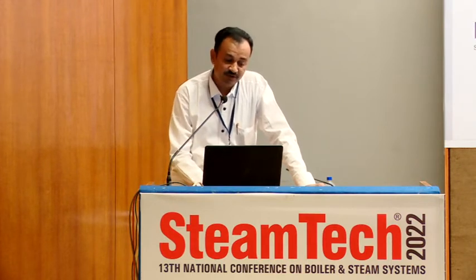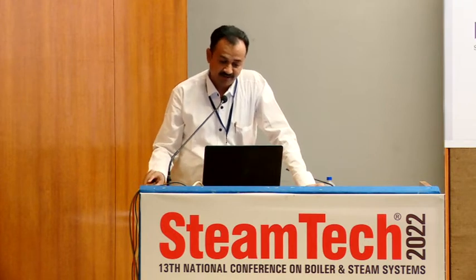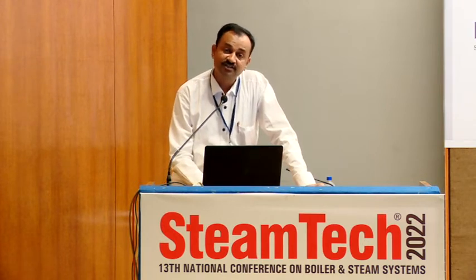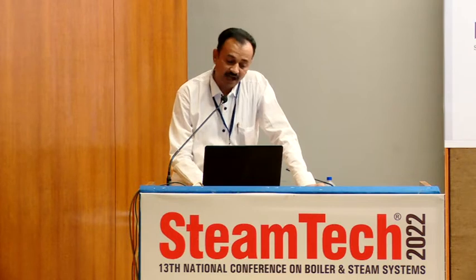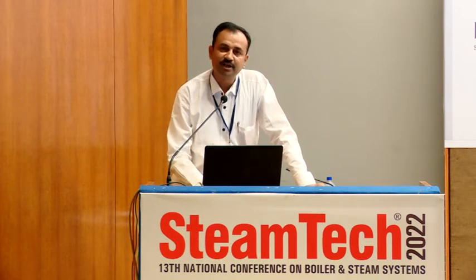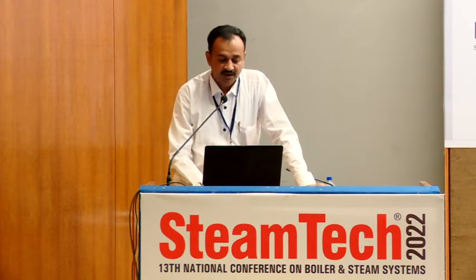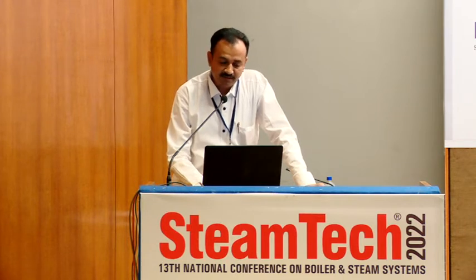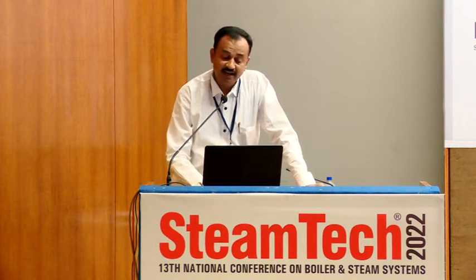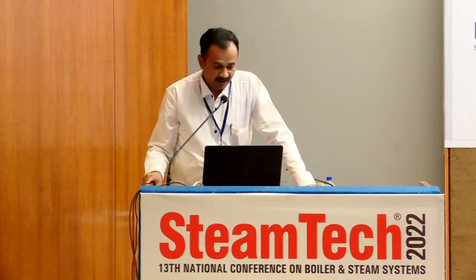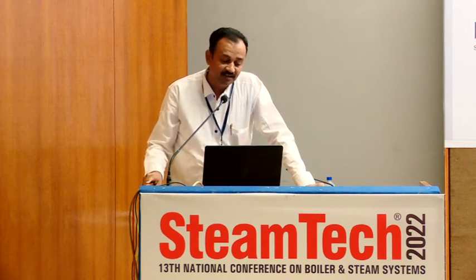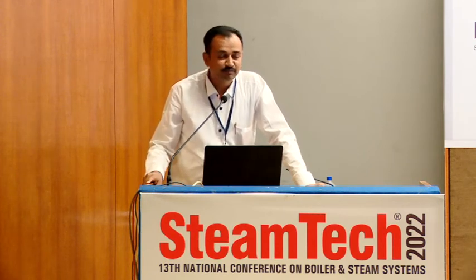And what it says for the boiler capacity of 5 ton, where the fuel price was 6.5 rupees in the pre-COVID era and now, in the month of January 2022, it was 11 rupees. So you can imagine, for the 5 tonner boiler he is losing 62 lakh rupees, which was earlier 37 lakh, and for the 10 tonner 1.2 crore, and imagine for 15 ton, 1.87 crore. So it's a huge loss.